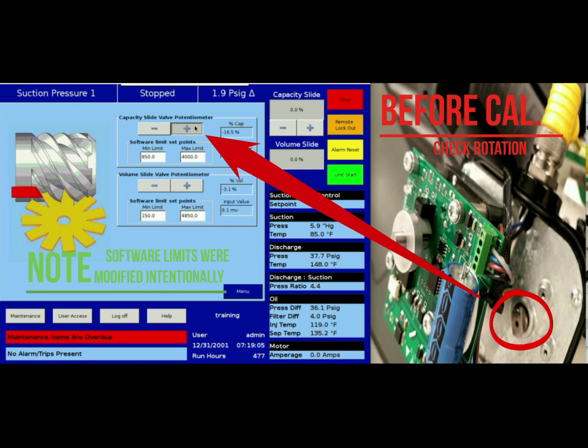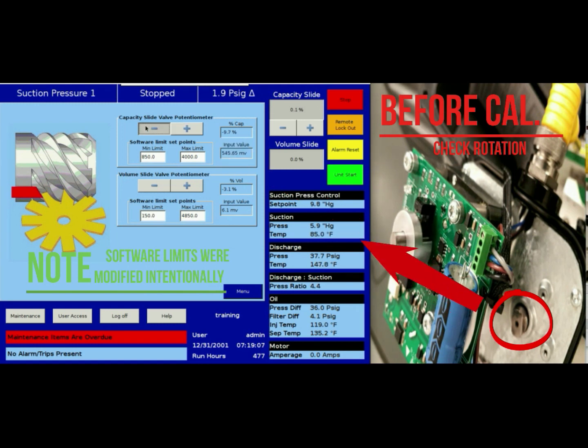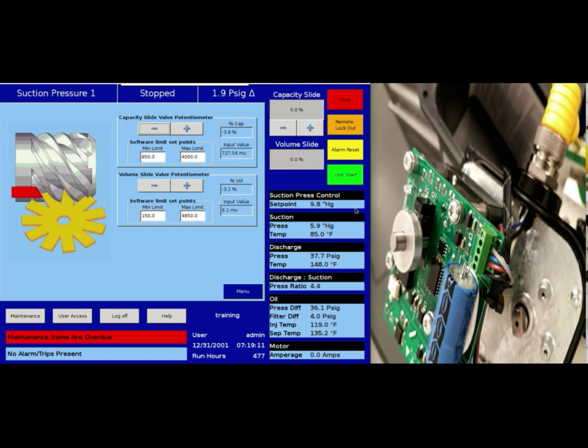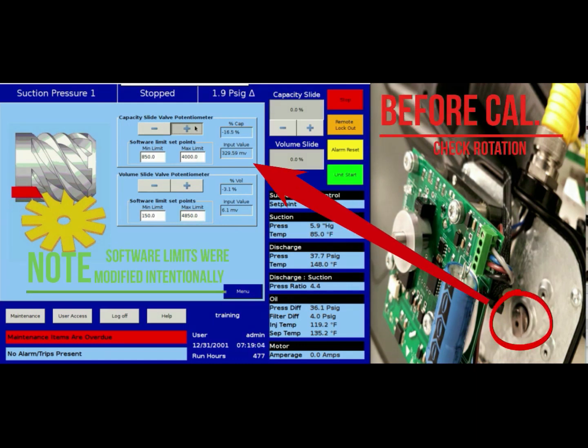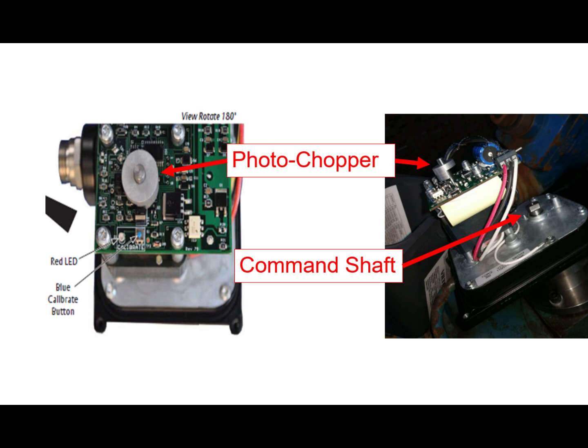Here's an example of checking the rotation of your command shaft. First, we have identified which actuator we are working on, in this case the volume actuator. Next, we are going to press and hold the plus increase button, and at the same time look back at our command shaft to verify the rotation. Please note that there are two rotating objects on this actuator. To the left, your command shaft, and to the right, our photo chopper. We want to make sure that we are looking at our command shaft.